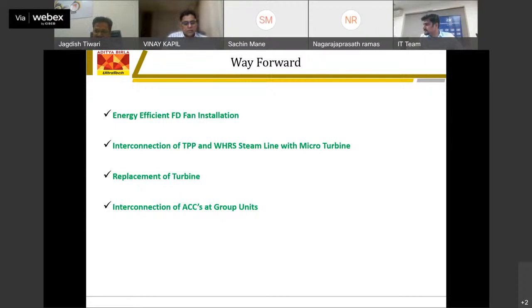We have also approved capex for replacement of the turbine with enhanced capacity. Our present turbine is 27 megawatt, and we have taken capex for a 30 megawatt turbine that will be installed on the same foundation, and that will give us a saving of about 0.1 kg per kWh reduction in steam consumption. That will reduce about 80 kilocalorie per kWh. And also, on interconnection, we have taken one initiative at our group level, sir.